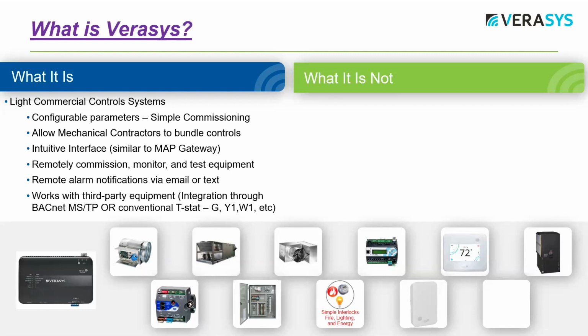The other optional control method or connection method would be using BACnet for a BACnet-enabled piece of equipment, but we have to make sure that's not used in a VAV or changeover bypass application. For those applications, if we have a rooftop unit or an air handler, it must have a conventional thermostat interface, or we're going to be looking at embedding controls in the equipment, and that's not going to be a very easy proposition for all but the most experienced installers of building automation systems.